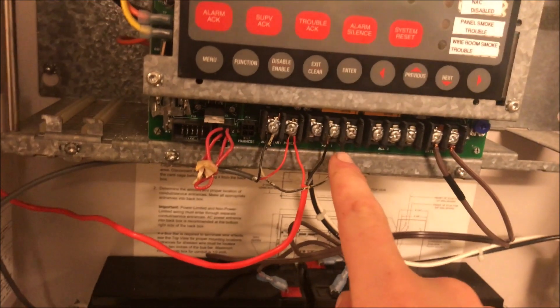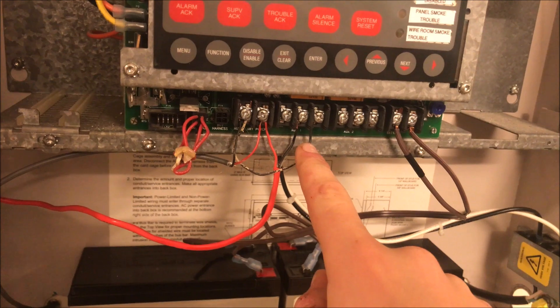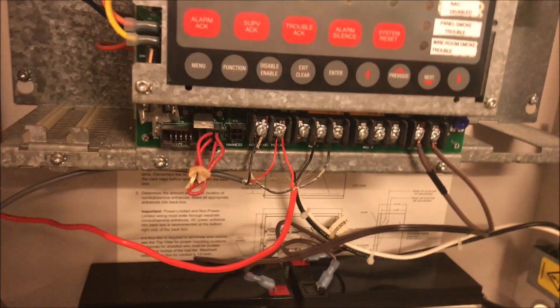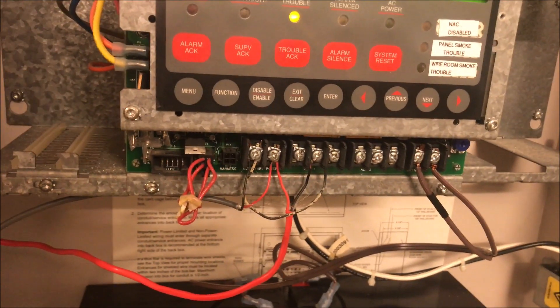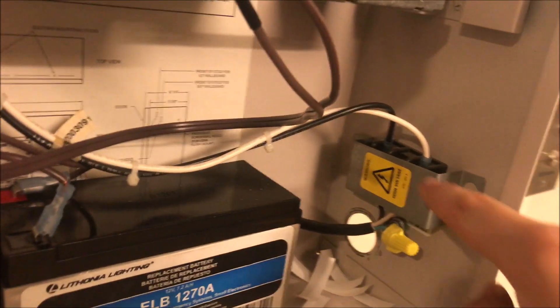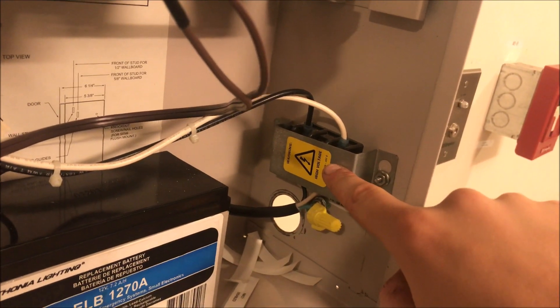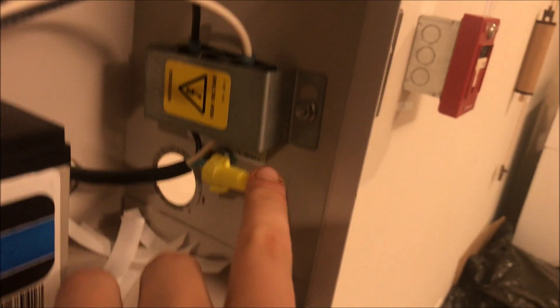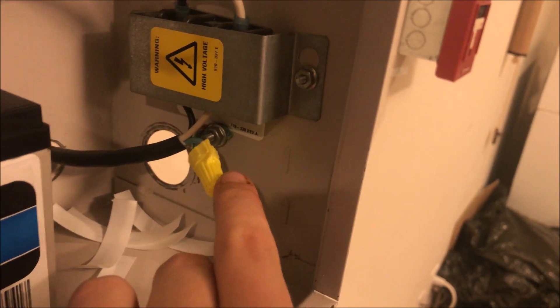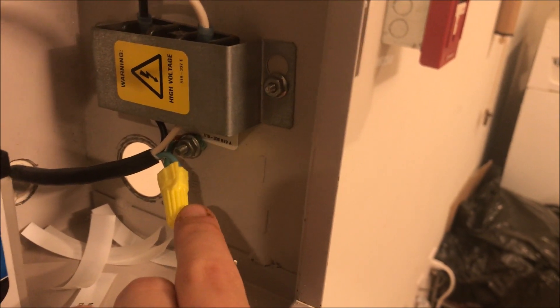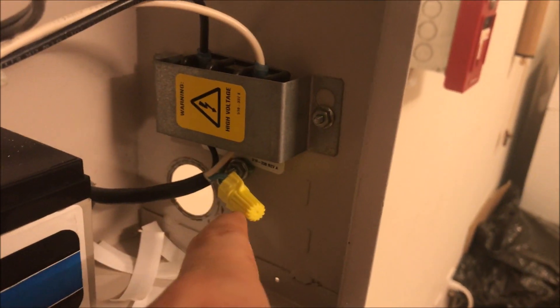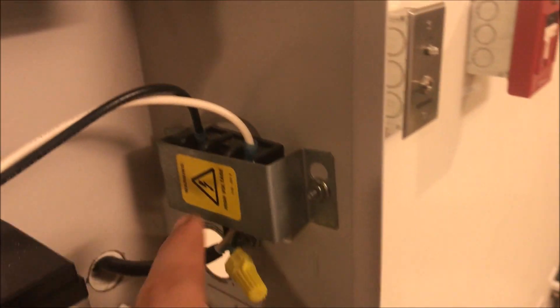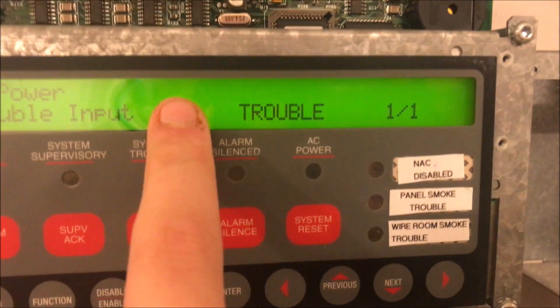The door holder is going to close. What happened is that relay just opened, which cut the power and allowed the door holder to release. Down here is your AC input. Your ground goes to the ground here—yours may look different than mine because mine was cut haphazardly. Then you have your hot and neutral coming in, and those go up to your hot, neutral, and that goes up to the transformer back behind the panel.